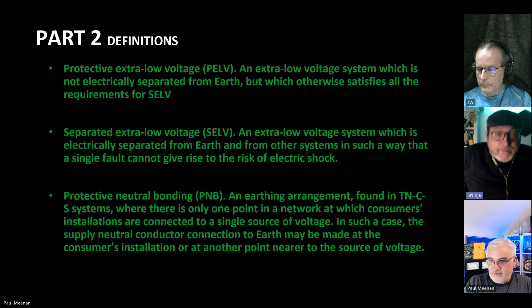Yeah, but okay - residual current detecting device, RDC-DD. We've covered this before in past podcasts. It's now defined as a detection device having at least the functionality of detection evaluation of 6 milliamp DC, kind of the equivalent of the A-type RCD.